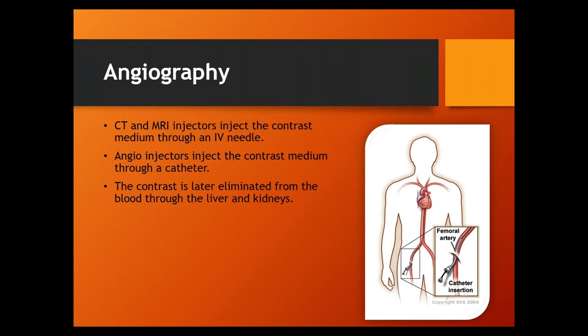Angiographic procedures don't use IV needles - ever. They use catheters, inserted typically into the femoral artery or femoral vein. The catheter is two or three feet long and very thin, and it snakes up into a particular body part - the heart is a very common target. They'll snake the catheter tip into one of the four chambers of the heart, then during the actual X-ray shot they fill that chamber with contrast. Angiographic injectors typically have much higher flow rates - up to 40 or 50 milliliters per second - compared to CT and MRI injectors which max out around 10 milliliters per second through an IV needle.